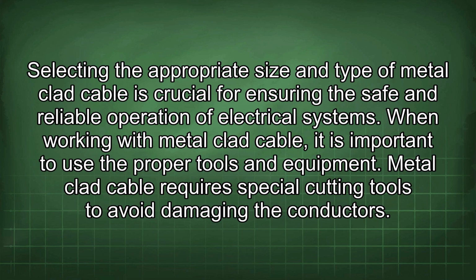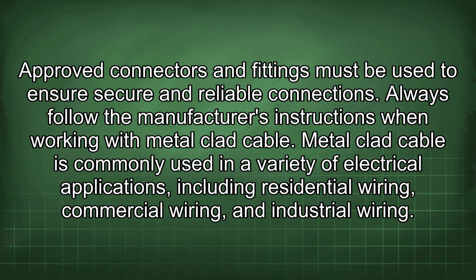When working with metal-clad cable, it is important to use the proper tools and equipment. Metal-clad cable requires special cutting tools to avoid damaging the conductors. Approved connectors and fittings must be used to ensure secure and reliable connections. Always follow the manufacturer's instructions when working with metal-clad cable.